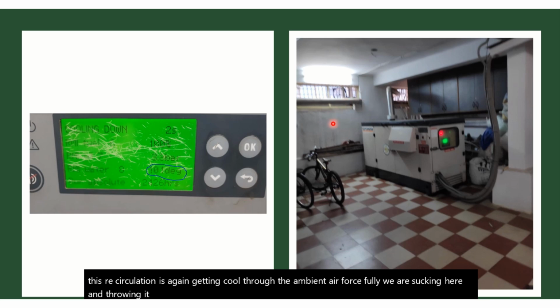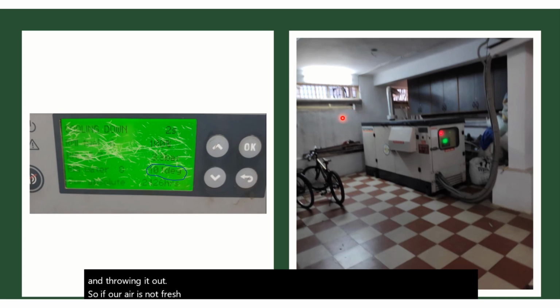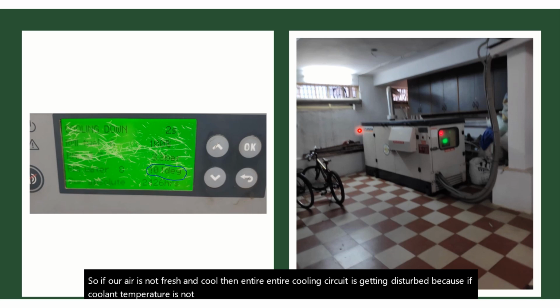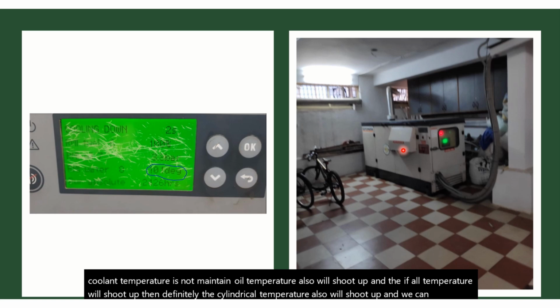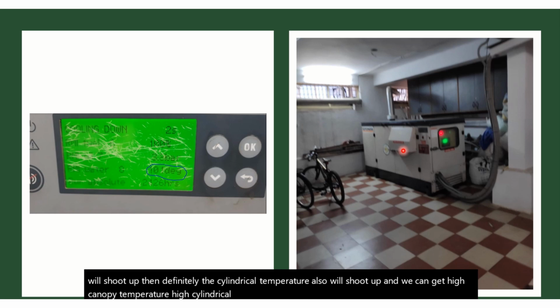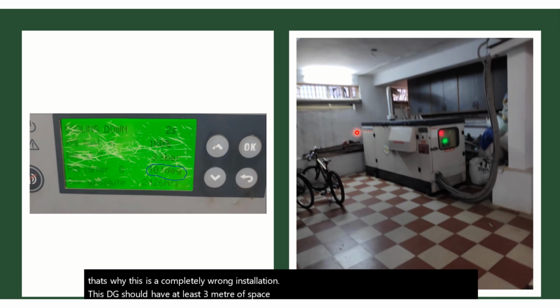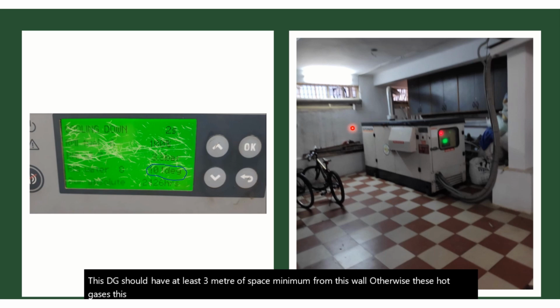So if our air is not fresh and cool, then the entire cooling circuit gets disturbed, because if the coolant temperature is not maintained, the oil temperature will also shoot up, and then definitely the cylinder temperature will also shoot up, and we can get high canopy temperature, high cylinder temperature, high water temperature. That's why this is a completely wrong installation, and this DG should have at least 3 meters of space from the wall. Otherwise the hot air coming out from the radiator side will again strike the wall.